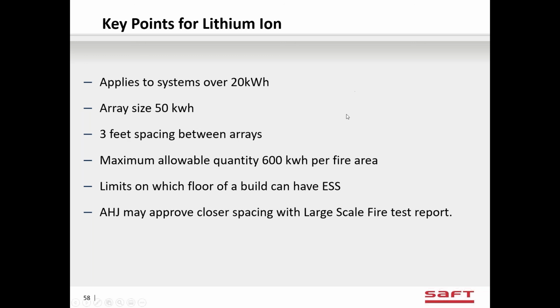They have a maximum allowable quantity per fire area of 600 kilowatt hours. So 600 kilowatt hours, and then firewalls, like a 2-hour firewall, and then another room for more 600 kilowatt hours. This is a very big battery. For us at the data center level, this is about a 2 megawatt battery. This would be probably 18 or 20 cabinets. This is a big battery.